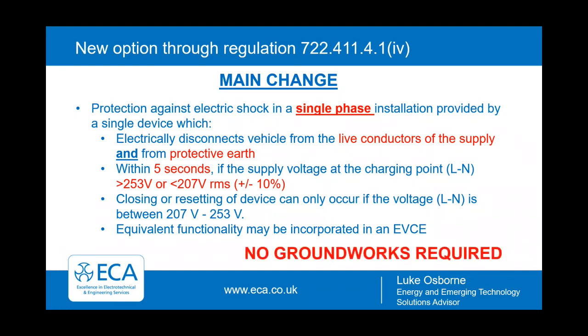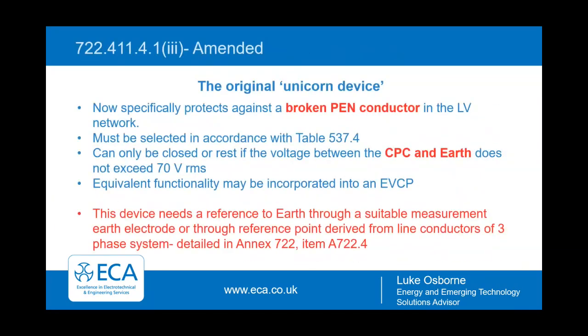So importantly, this then means that no groundworks are required. There was also a change to the original Indent 3, which was the unicorn device I mentioned earlier. This now is sited to specifically protect against a broken PEN conductor. Like I said, this is monitoring the difference between the CPC and the earth, ensuring that it doesn't exceed 70 volts RMS. But as mentioned, this does use an earth reference electrode.